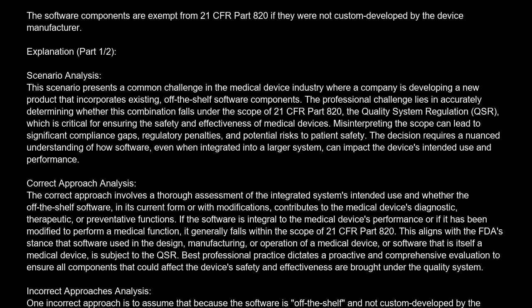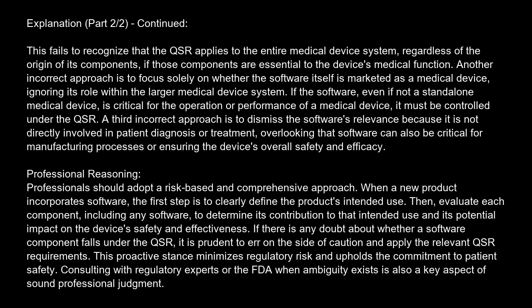Incorrect approaches analysis. One incorrect approach is to assume that because the software is off the shelf and not custom developed by the company, it is exempt from the QSR. This fails to recognize that the QSR applies to the entire medical device system, regardless of the origin of its components, if those components are essential to the device's medical function.